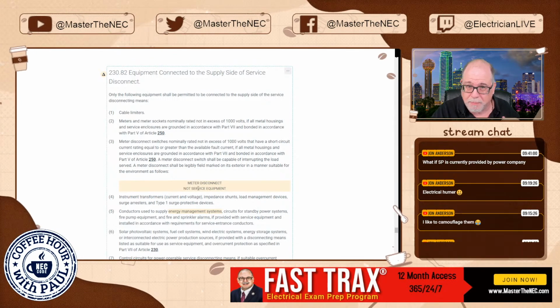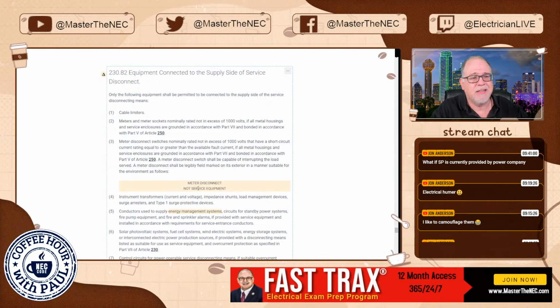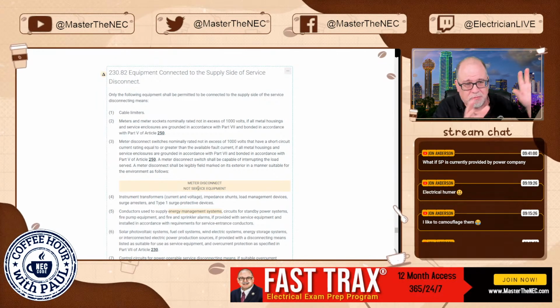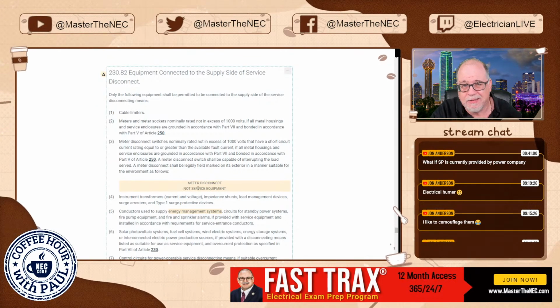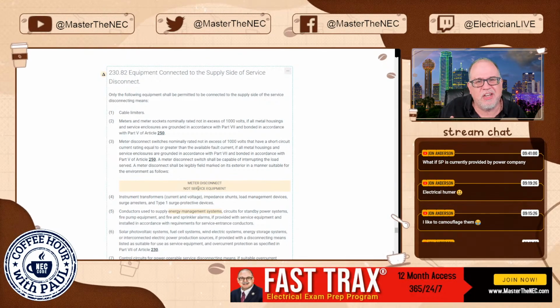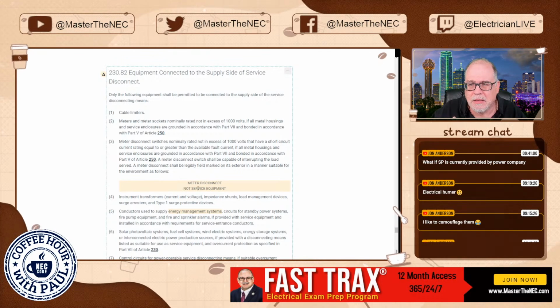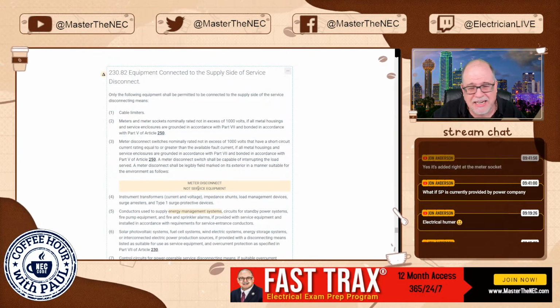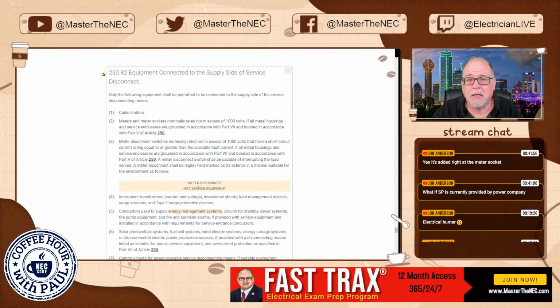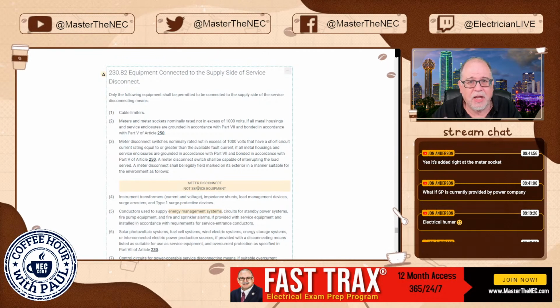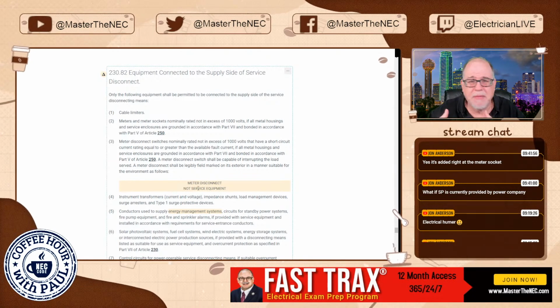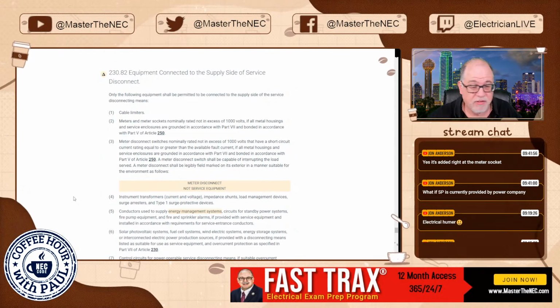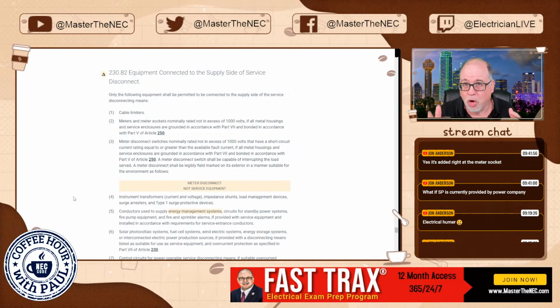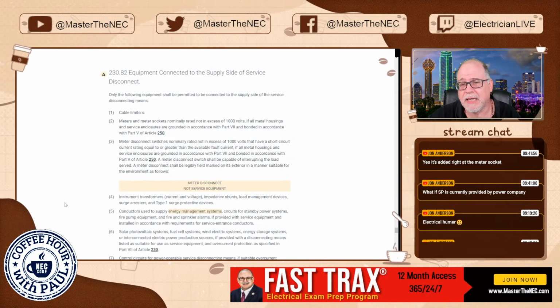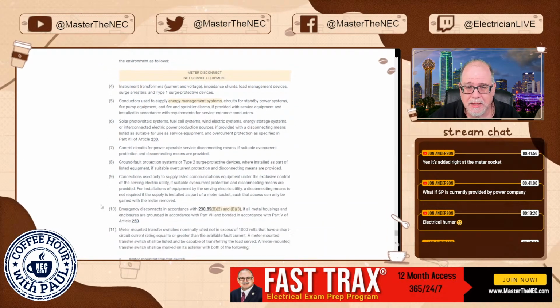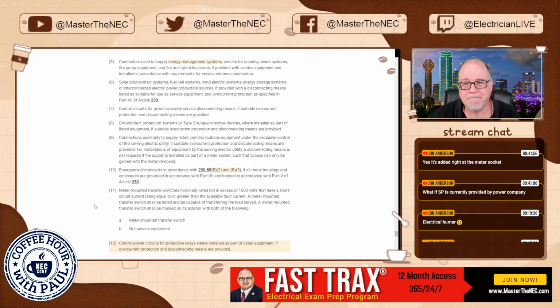And remember, if it's on the supply side of the point of attachment, like the service drop that goes up, then that's really outside of the scope of the NEC. So we wouldn't know, and the inspector wouldn't care. They just wouldn't know it's there. But if it's something that's done in the equipment, something that's done by the utility, and you can validate that and it meets all these rules, then I would say, okay. If it's done at the meter socket enclosure and you can show that that is a surge protection and it meets all of the criteria, then as long as it's a type 1 or type 2, and those would probably be type 1, then to me, it would be okay. You might have to show that to the AHJ, but nothing says that it can't be, right?